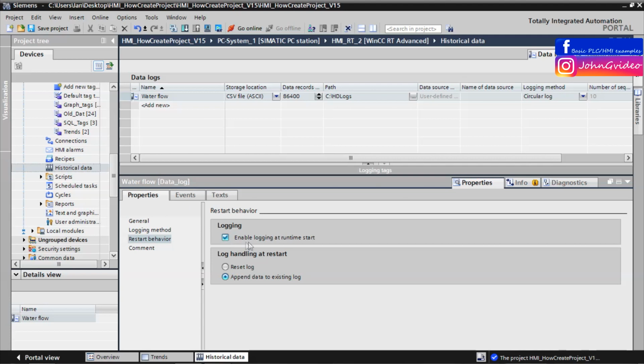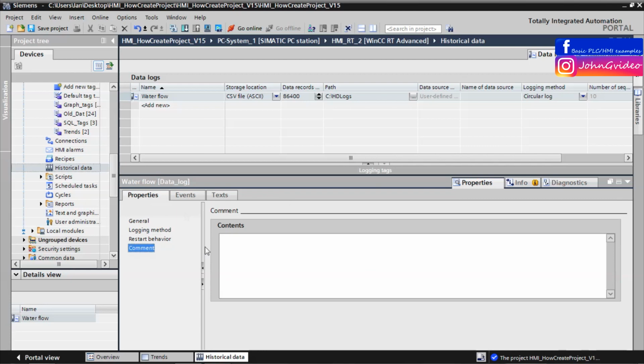Here we enable the logging at runtime start, because we want to log every value when the machine starts. And here you also have log handling at restart. For this we use append data to existing log, because we don't want to lose all the data after restarting. And some comments: this is a data log for water flow values and set point.